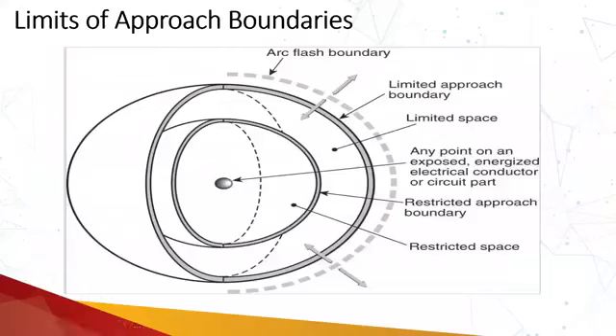Okay, moving towards the limits of approach boundaries. There are two types of boundaries covered in the standard. One is the arc flash boundary and the other is the shock protection boundary. The shock protection boundary is further divided into the limited approach boundary and the restricted approach boundary.